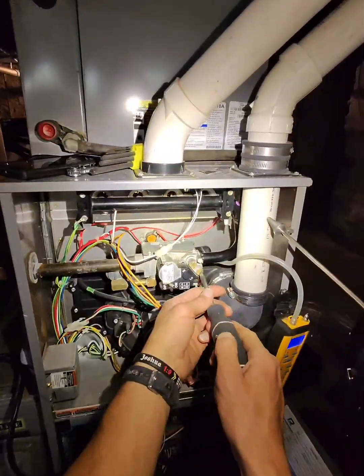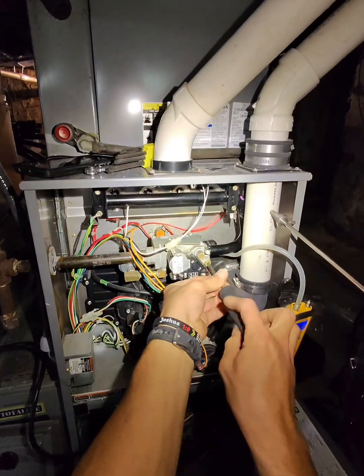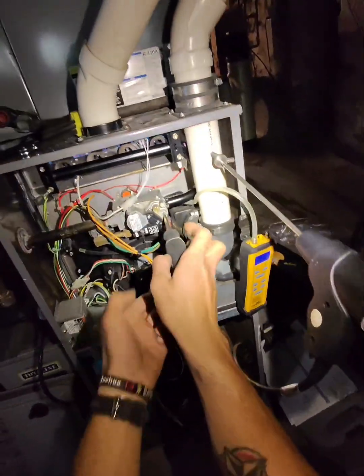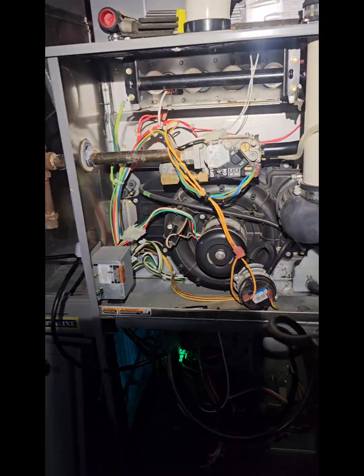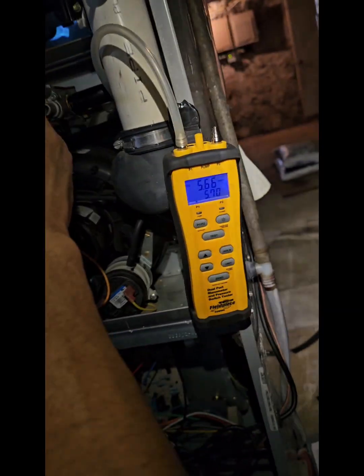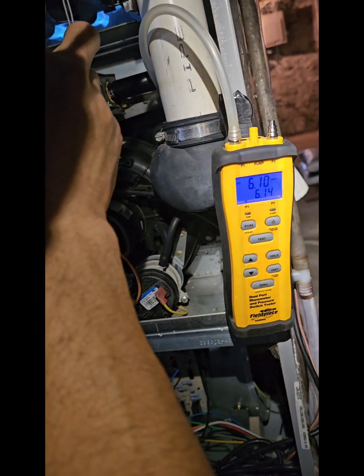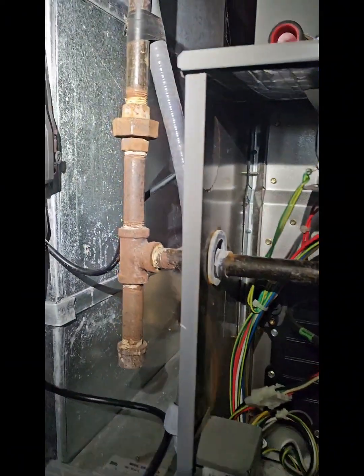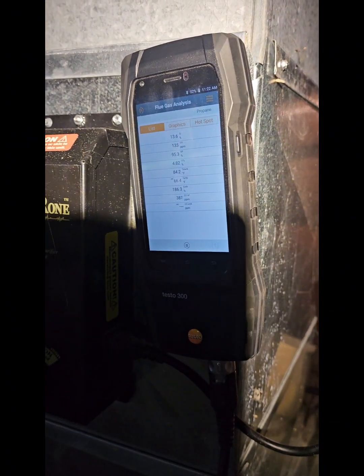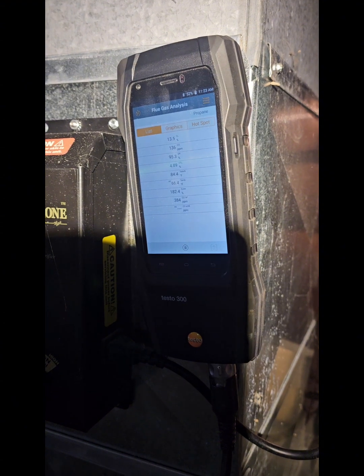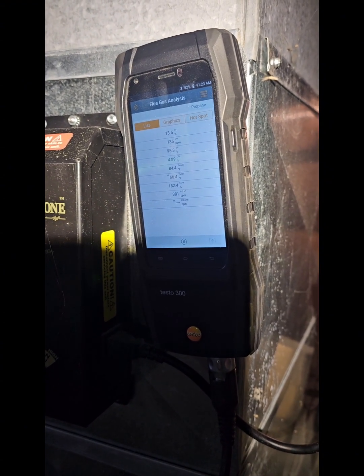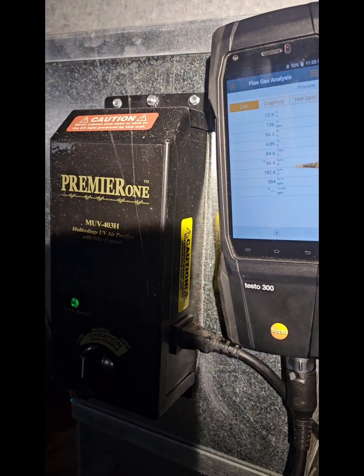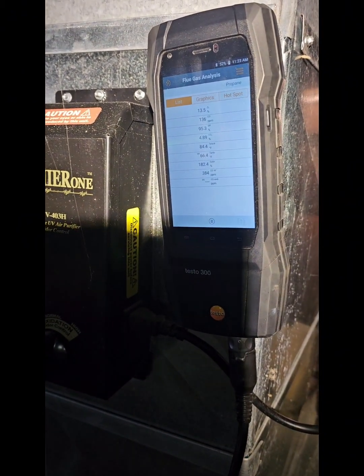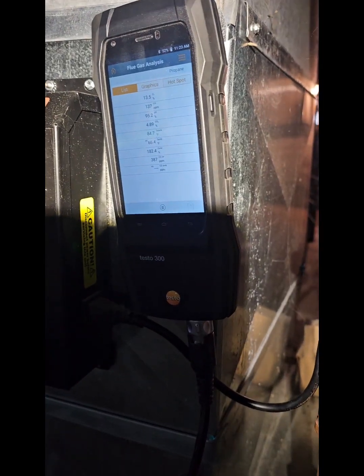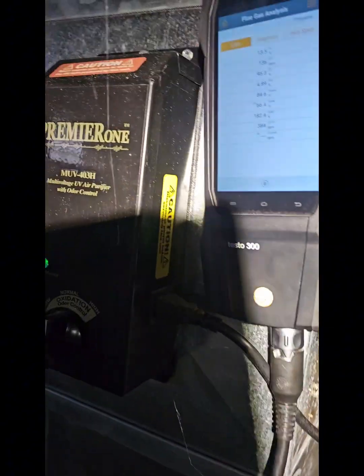Let's see what happens when we turn up the gas pressure here. See if the CO goes down, and then we'll also jump it into high fire and see what we see. Okay, so let's go ahead and adjust the gas pressure here. Stiff adjustment. Alright, up at 6.1 inches of water column, and we're not getting really any fluctuation. The CO is not coming down any. The excess air right here has gone down slightly from 195, but not significant enough to relieve any worry. Not a significant enough drop to say, oh, well, now we don't really have to worry about that.